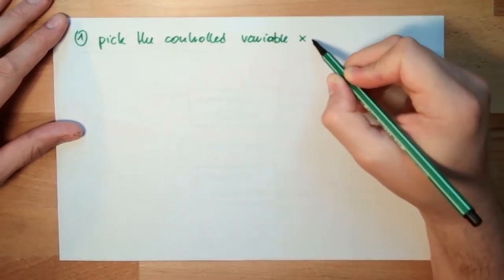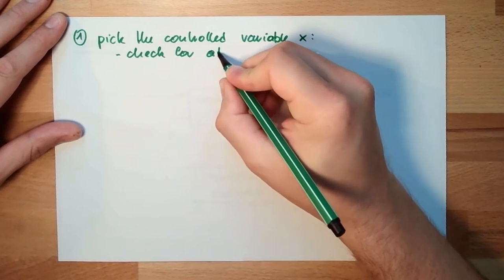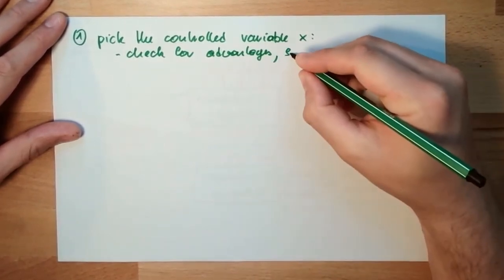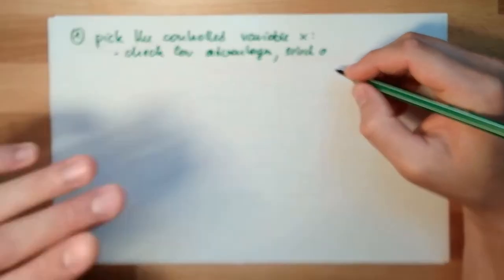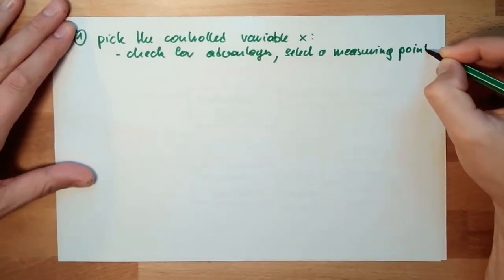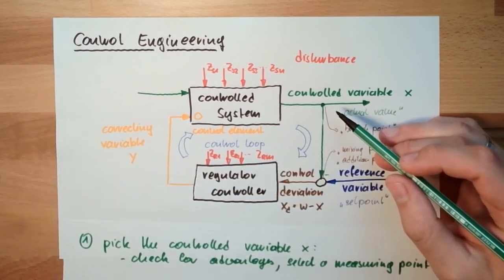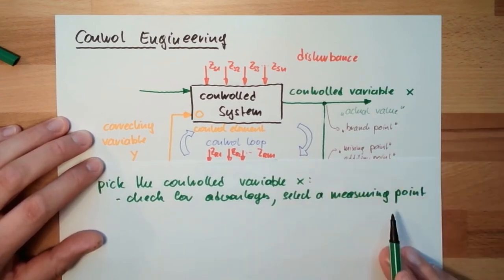So the first thing is: pick the controlled variable X, and check for advantages. Then we select a suitable measuring point. This is quite important because I have to measure the control variable. If I'm not able to find a suitable measuring point, then I can forget the whole thing. If I can select the measuring point, then my control variable is fixed.